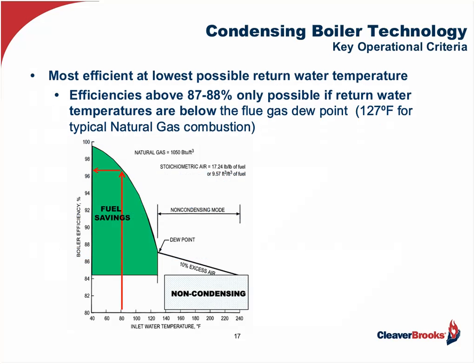Now, this is one of the curves I really want people to focus on, because this really explains why we use condensing boilers and why we want to look at that delta T and supply water temperature. This is an efficiency curve. And by the way, this efficiency curve doesn't apply to condensing boilers only; this is any boiler. If you stay above 130, you'll notice the best you can get is about 87% efficient. And as your return water temperature increases, it actually goes down. Once we hit that 130 or 127 degrees, that's where condensing starts to occur. Now, the important thing to remember here is it starts. But to maximize efficiency, we want to maximize our condensation. So the colder the water to the boiler, the better. And you can see how that efficiency curve just climbs. And in fact, if we had 40 degrees, we'd be very close to 99% efficient.